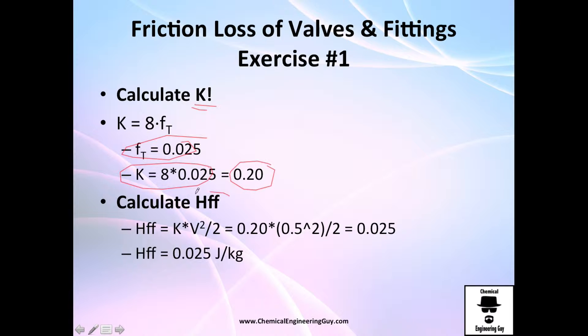But we are not calculating K value—we are going to calculate the energy loss due to this friction. And this K value is 0.20. The velocity we have, divided by 2, and it is right here: 0.025 joules per kilogram is the loss that you're going to expect in that gate valve.